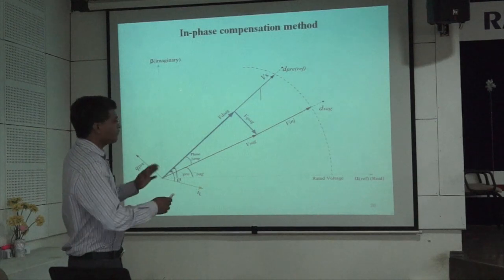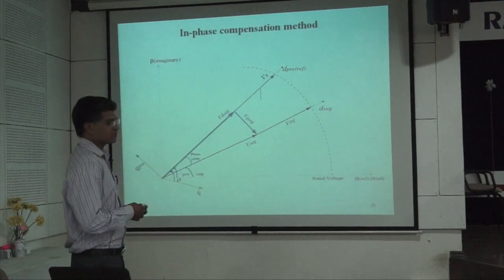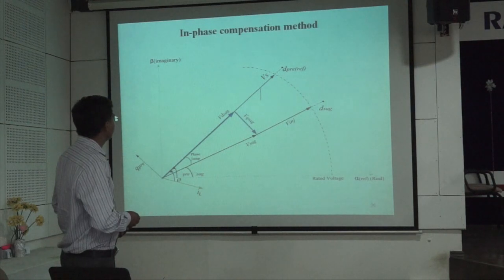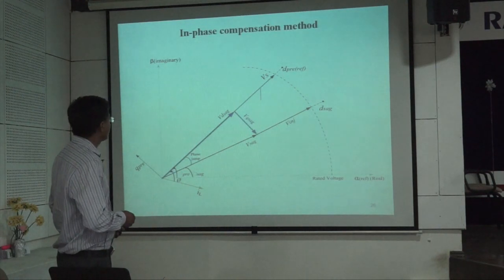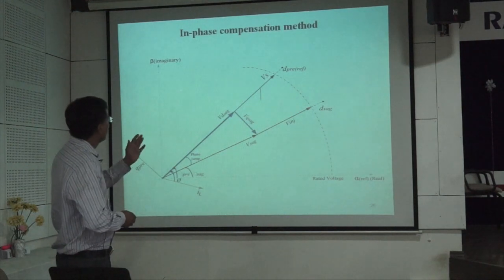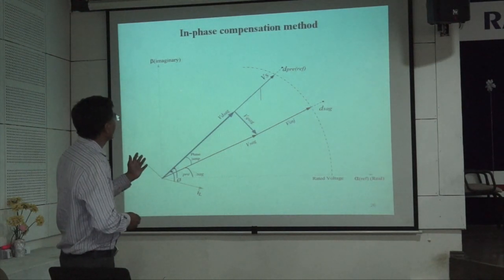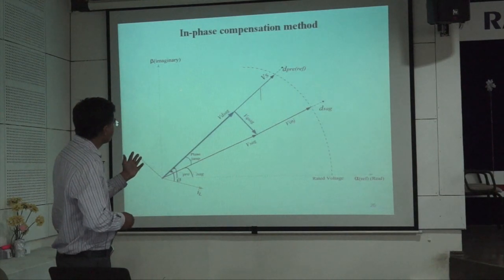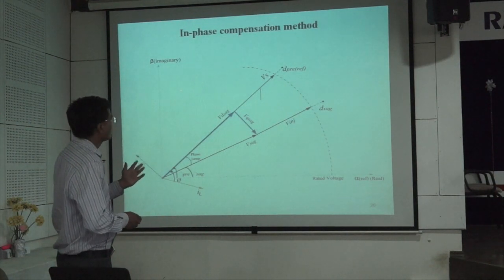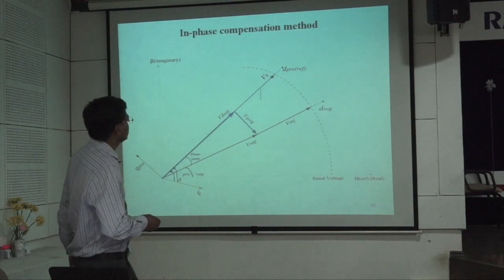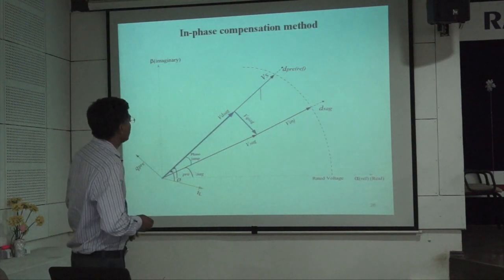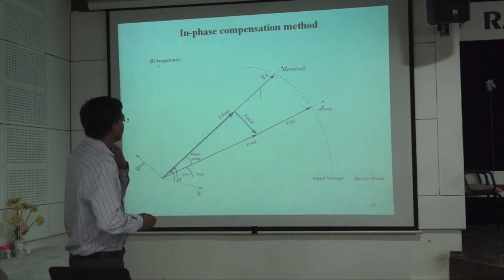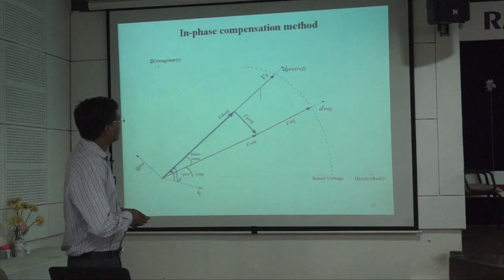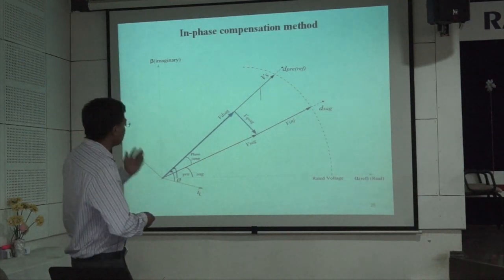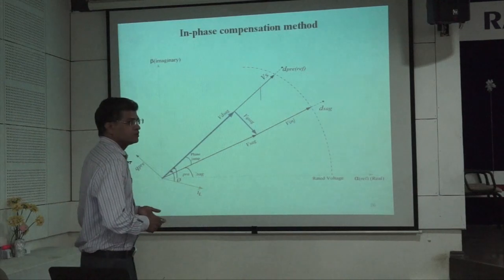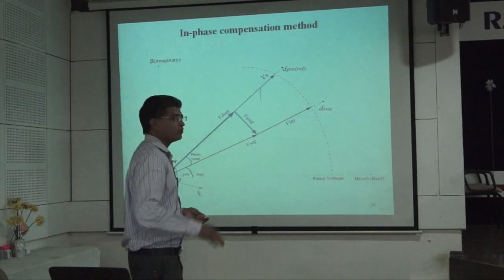So there are various compensation methods, such as the in-phase compensation method. This is the source voltage where there is a decrease in the voltage, that is V sag. This is the source voltage, decrease in voltage V sag. It is derived into components, D component and Q component. So this V sag is VD sag and VQ sag. This is the injected voltage. If we inject the voltage in this fashion, we can compensate the magnitude only. We cannot compensate the phase. Due to this type of injection, a lesser value of injected voltage is required, so we can reduce the rating of the DVR.